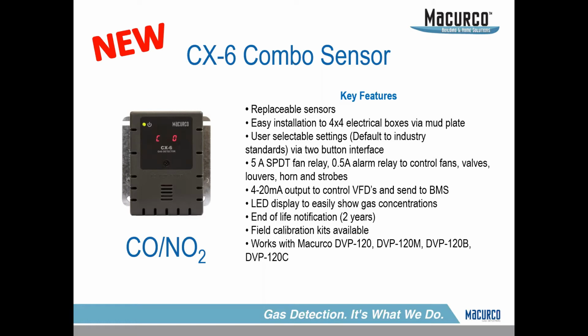The single 4 to 20 milliamp loop basically takes the highest value of that 4 to 20 milliamp output. So it says here, 4 to 20 milliamp output to control VFDs or send to a BMS. In this case, if the CO is higher than the NO2 in terms of its milliamp output, you're going to see that reading. A lot of people don't do that. You'll have to have multiple outputs or multiple wires for the different outputs in this 4 to 20 case. We were able to come up with a simple way, less wire, less conduit type stuff to help with the cost. Everything that we do here is field calibratable.